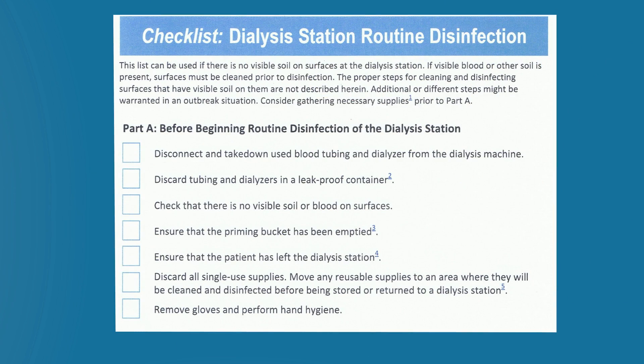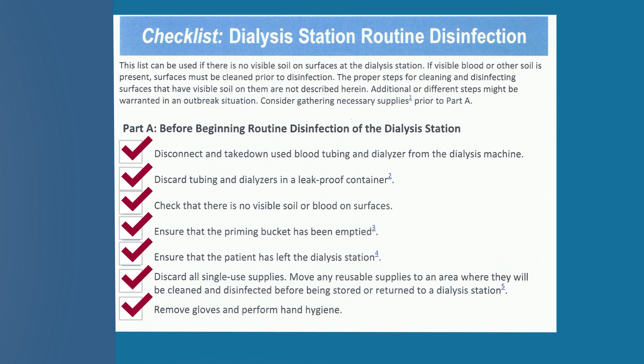Part A of the checklist has several key reminders, including the disconnecting, taking down, and discarding of used blood tubing and dialyzers in leak-proof containers. Checking for visible blood or soil, ensuring that the priming bucket has been emptied, that the patient has left the station, and discarding single-use supplies. Reusable supplies such as clamps should be moved to an area where they will be cleaned and disinfected before being stored or returned to a dialysis station.